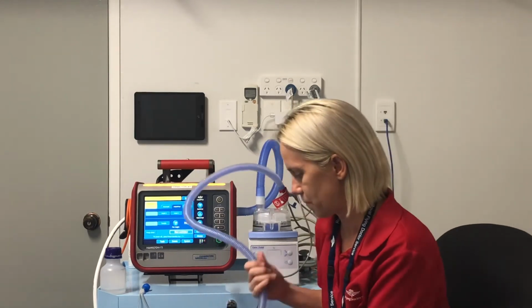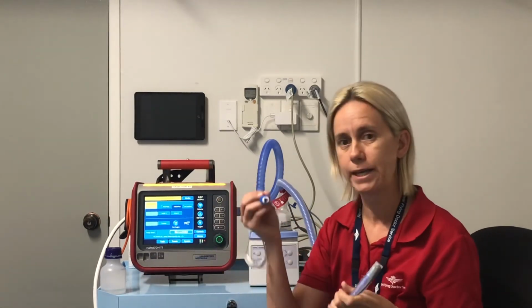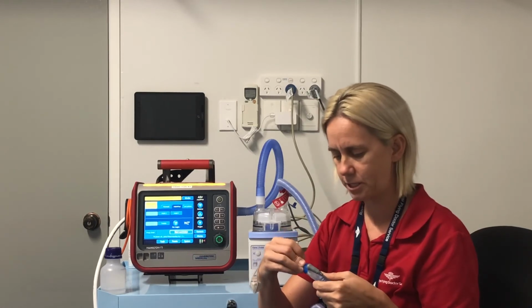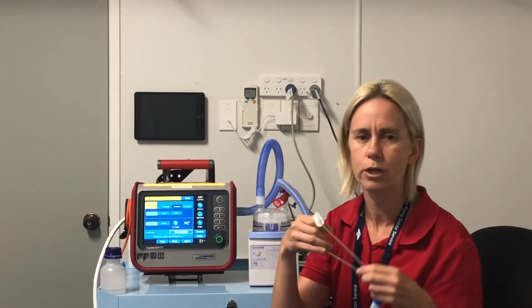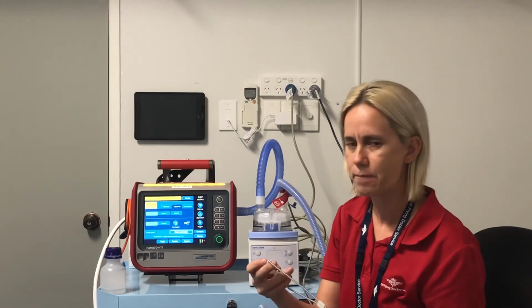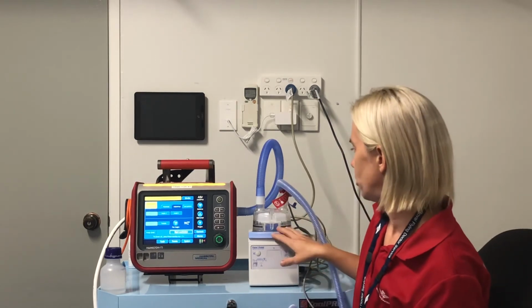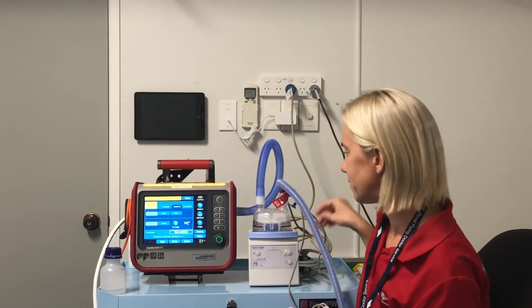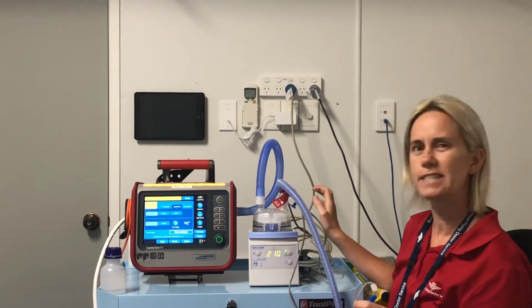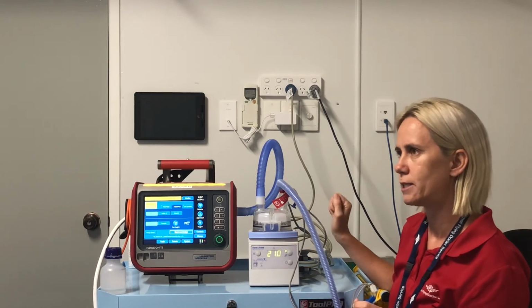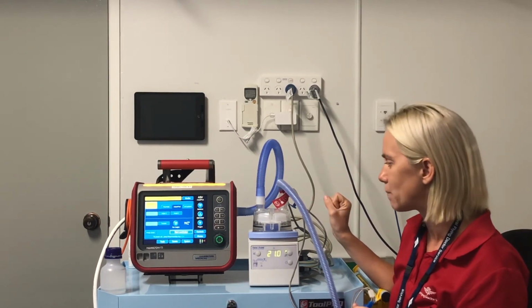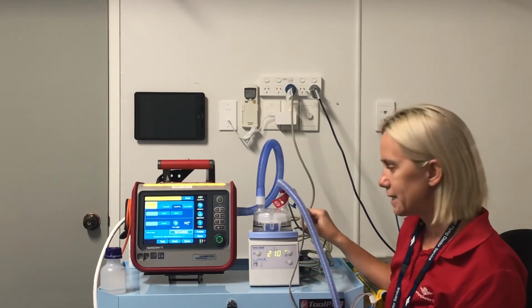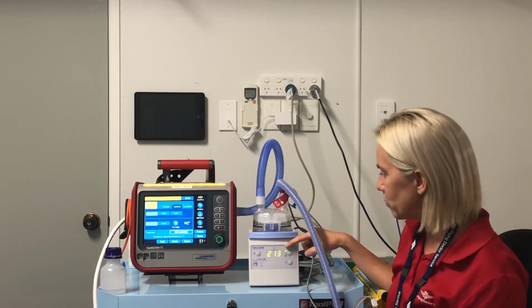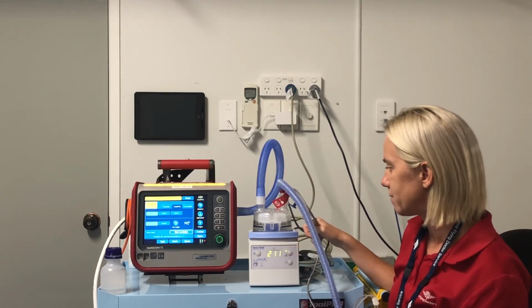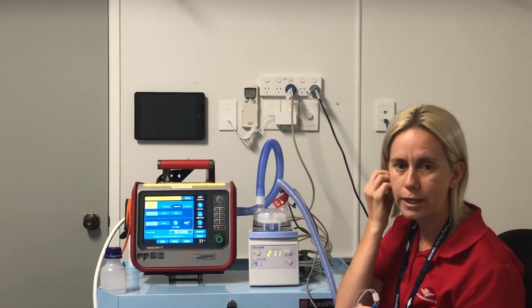Okay, the setup is almost complete. The only other thing that you need from here on is appropriate sized nasal cannula for your patient. Just for demonstration purposes today, I've just got some pediatric ones. So once it's all connected up, ultimately what we'll do is switch on the humidifier. It will come up in invasive mode, generally that's what it reverts to. It does take a few minutes to warm up, so just keep this in mind. If your patient's already on high flow, leave them on that until you've got this set up. So that'll do its little test. So we've got the top one, which is invasive, which it ultimately reverts to, and the bottom one is non-invasive. So once that's done, we'll let it warm up.